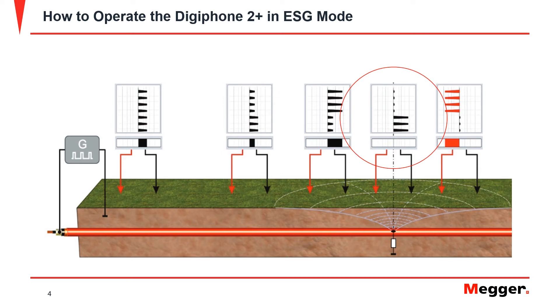If the fault is exactly between the two earth spikes or exactly to one side, the indicator unit does not display a reading. If the fault position has been passed by, the polarity changes. The signal on the indicator unit points in the opposite direction.